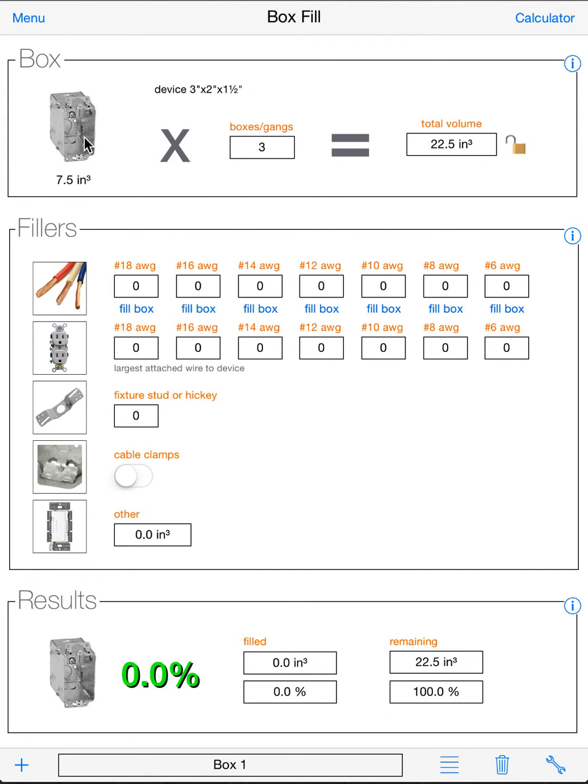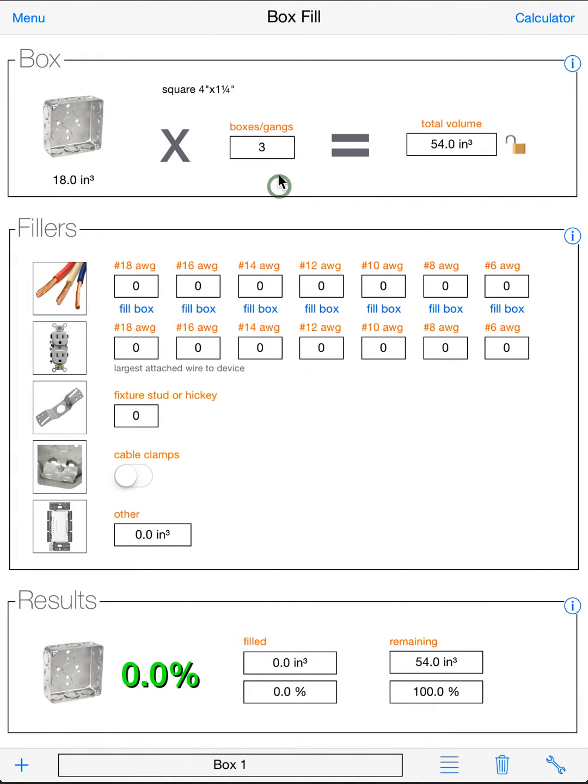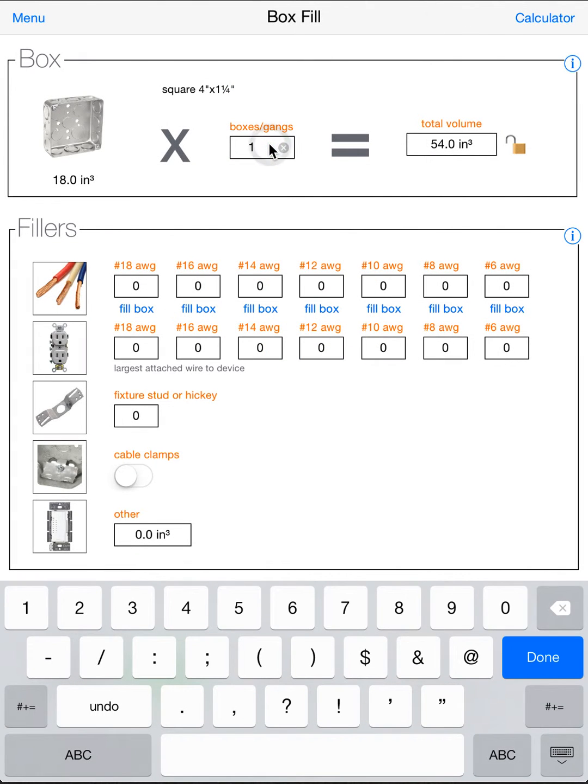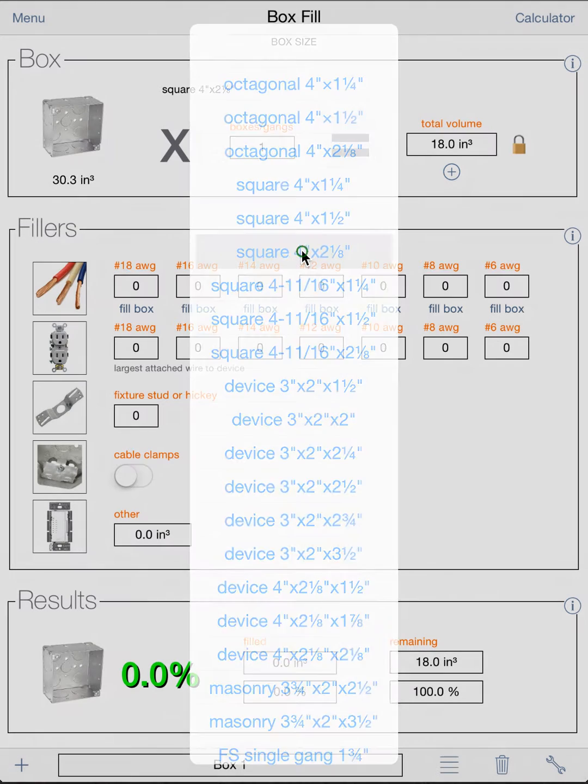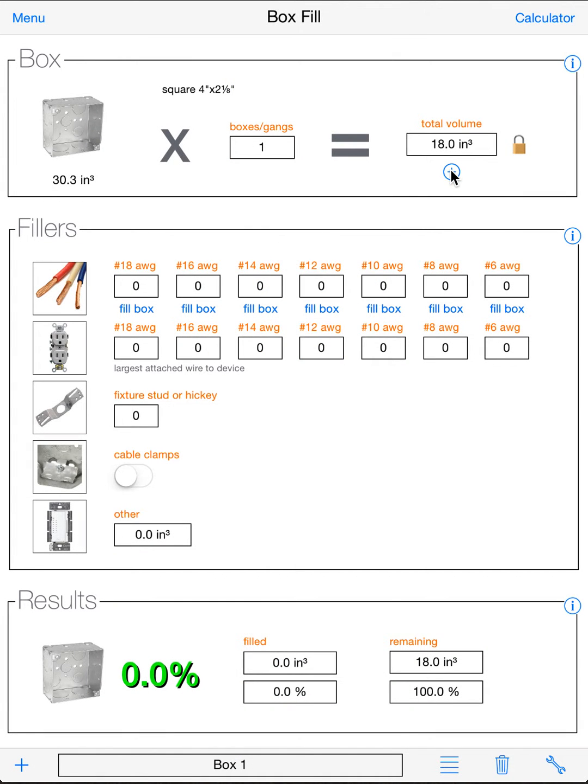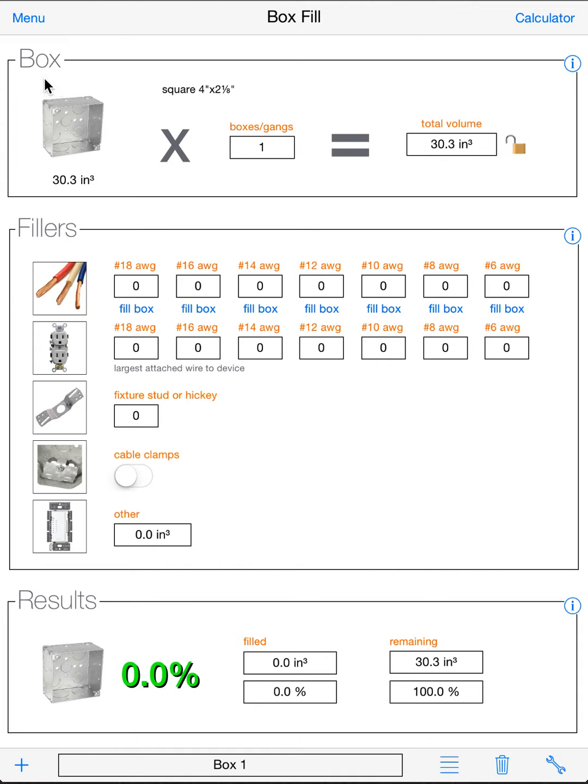Now another way to do your box is you can lock and compound a box. So we can go to a square box, for example. We can go to a single gang. And then if we wanted to add a bigger extension ring, we can lock this value here, the 18. So now it's locked, because the little lock is locked. And we can go to another box. So let's say we want to add a deep extension ring. And now we can just hit the plus button. And that'll add that 30.3 cubic inch box onto the one we already have. And you can keep doing that to compound a box. And then later on when you want to go back to your normal boxes, you just hit your lock again to unlock it. And that'll just do whatever box is selected. So that's how you select your box.